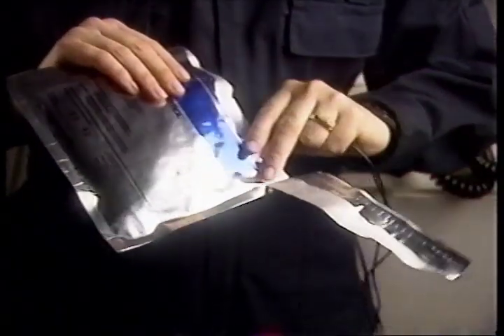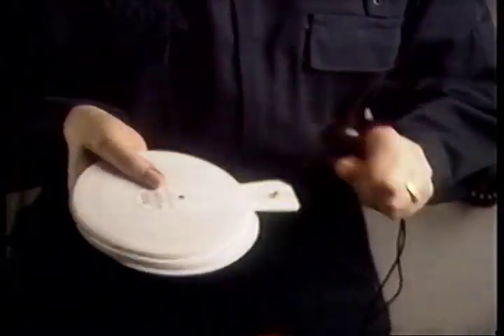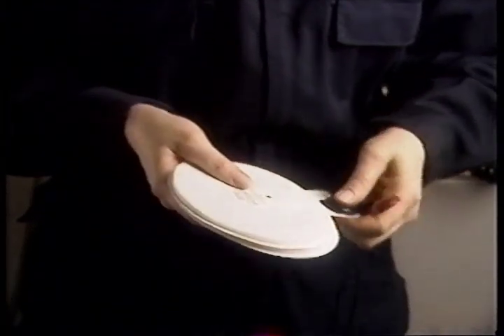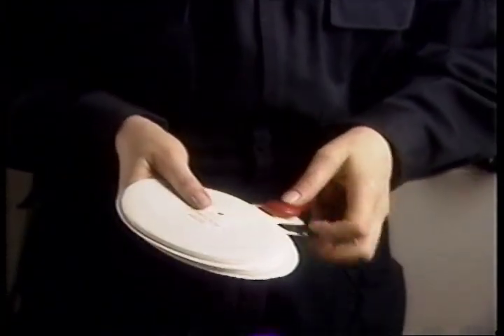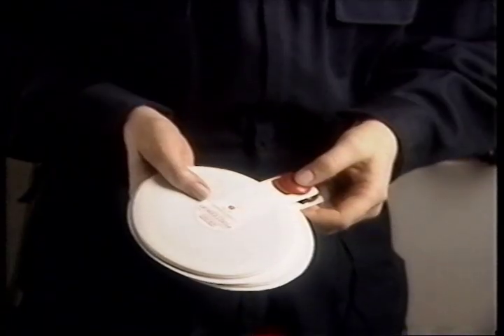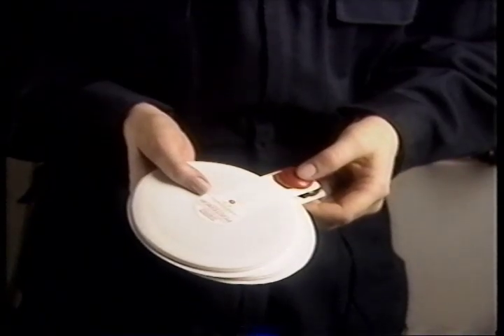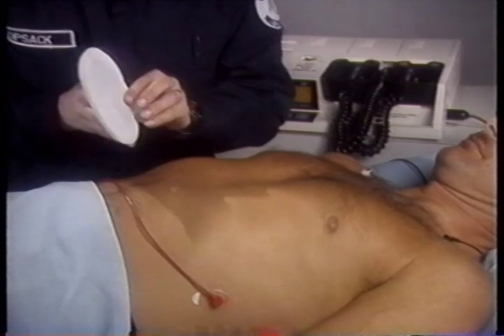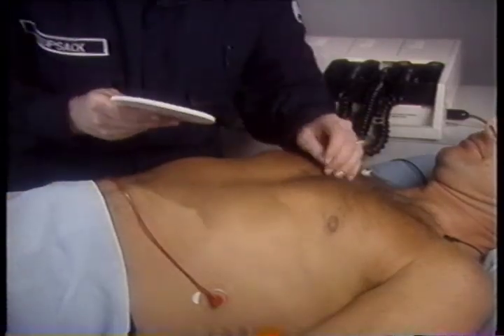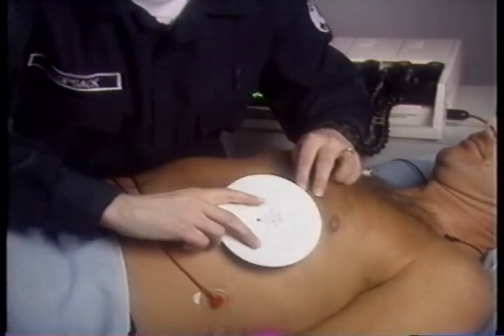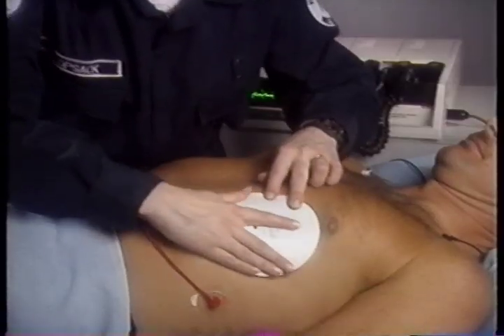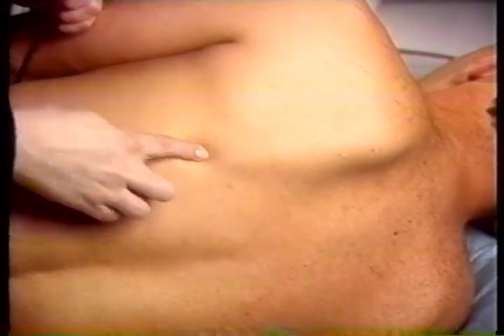Next, insert the pacing cable into the receptacle on the left side of the LIFEPAK 10. It must be firmly seated to operate. Connect the pacing cable to the quick-pace pacing electrodes. Match the connector color with the electrode color. Make sure that the connectors are firmly snapped into place. Place electrodes on the patient following the instructions on the electrode package. Place the black electrode on the anterior left chest at the cardiac apex in the V2-V3 ECG electrode position. Place the red electrode on the posterior left chest below the shoulder blade and to the left of the spine.